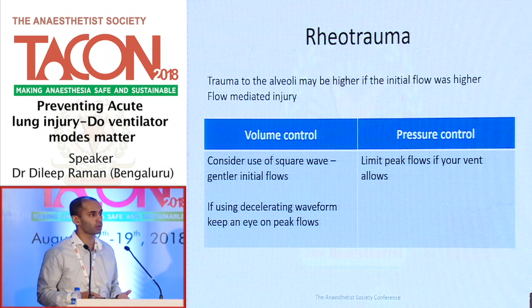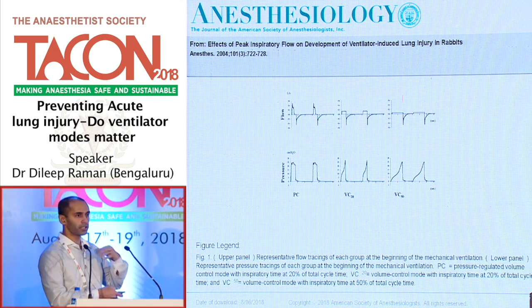In this paper that was published, again, this is not a human model, they showed volume control at 2 different flows and pressure control, and you can see here that the flow is markedly different. High flows in pressure control, lower flows in volume control here, and the lowest one here, when you adjusted the volume control to an IE ratio of 1:2, where your inspiratory flow is fairly low. Right here, this is the pressure control model. This is the volume control model with 20% time in inspiration. This is the volume control model with 50% time in inspiration, meaning a very gentle, slow flow rate. This is an animal study, but it's fairly instructive in the sense that even flows can potentially be damaging, because they equated all other factors. Plateau pressures, tidal volume, rate, everything was the same in both the lung models. The only thing that was different was the flow rate.